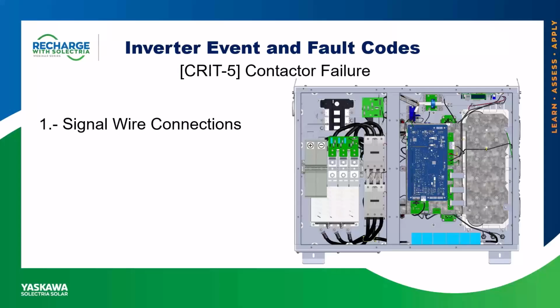What happens is if those signal wire connections on the right-hand side, they're red and white, are loose or making a false connection, that signal voltage is not going to be sent properly to the contactor, and it will result in the contactor not closing in and the inverter faulting out with this crit 5. So what is recommended is inspect your connections, A1 and A2, the little red and white wire, make sure they're tight, they're plugged in, and then power cycle the inverter to see if the error code goes away.